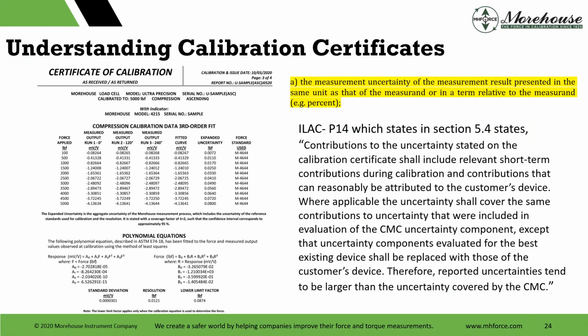So, understanding the certificates: the measurement uncertainty of the measurement result is presented in the same unit as the measurand, and we determine the relevant measurement percentage. Here we need to follow ILAC P14, which says contributions to the uncertainty statement on the calibration certificate shall include relevant short-term contributions during calibration and contributions that can reasonably be attributed to the customer's device. Where applicable, the uncertainty shall cover the same contributions that were included in the evaluation of CMC uncertainty, except that the uncertainty components evaluated for the best existing device shall be replaced with those of the customer's device. Therefore, reported uncertainties tend to be larger than the uncertainty covered by the CMC.